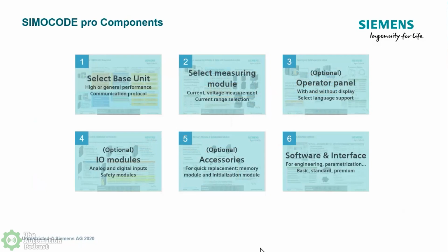You can see maybe your local handoff auto, and you can test and say, okay, I'm pushing start. Oh, yeah, I don't see the input changing state. So that means maybe my contact's bad. And then you can go, well, open up and change the contactor on the push button. And then we have the IO modules for analog, digital modules. As I stated, the inputs for the SIMOCODE is 24 volts DC.